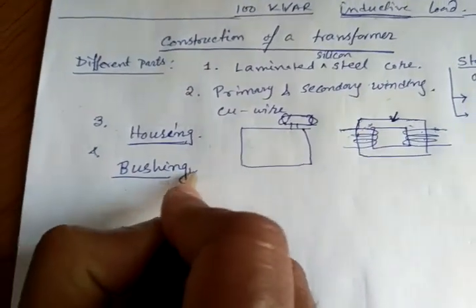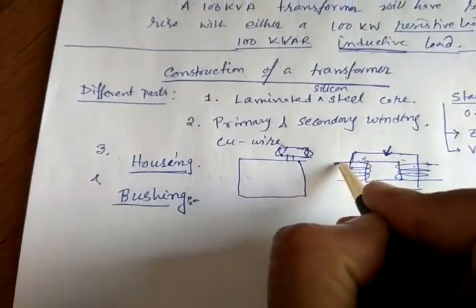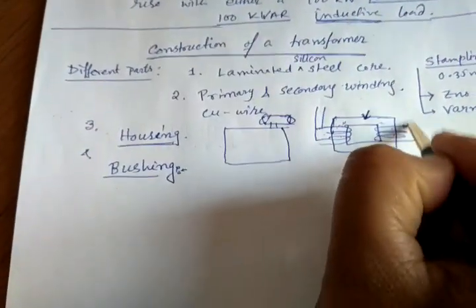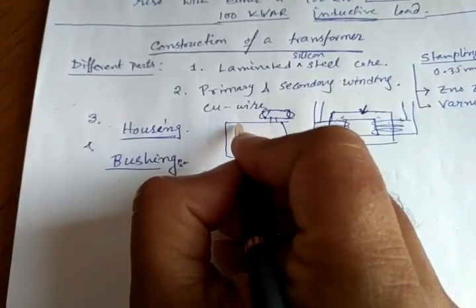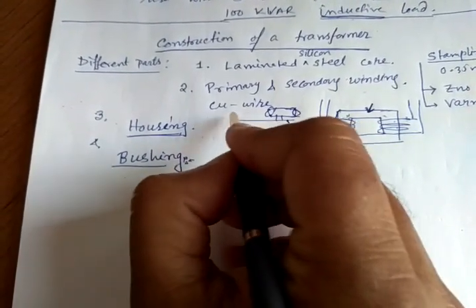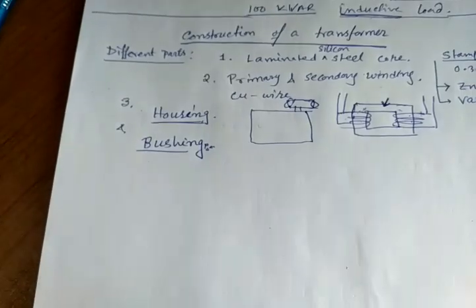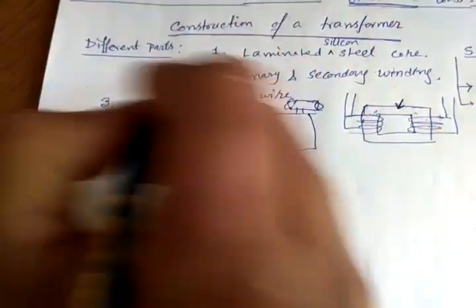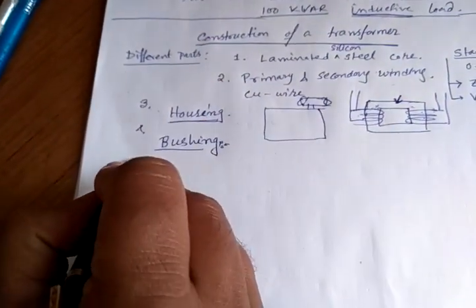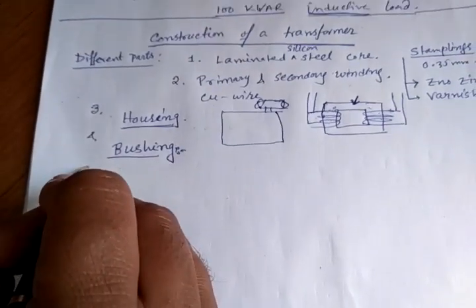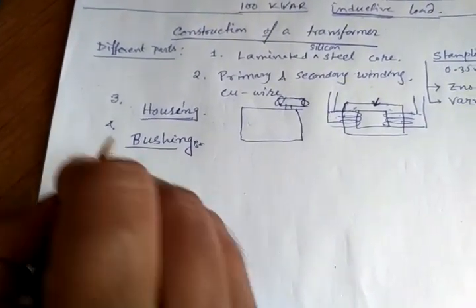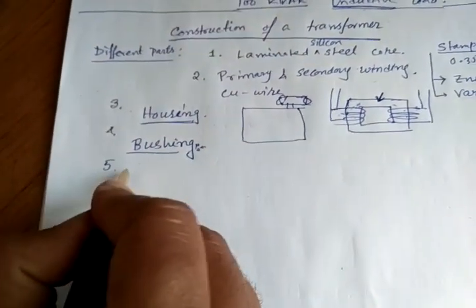And another part is the bushing. Bushing is nothing but the external contacts, two contacts from the primary, two contacts from the secondary. These are taken out of the box using some porcelain insulating material, that is called bushing, to connect to the outside circuitry. And another thing is, some external accessories are required for transformer oil cooling, etc.